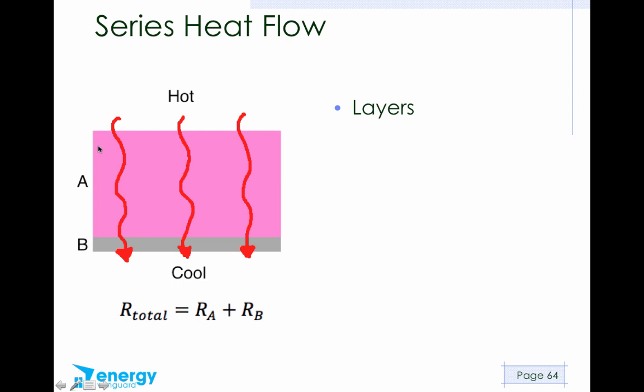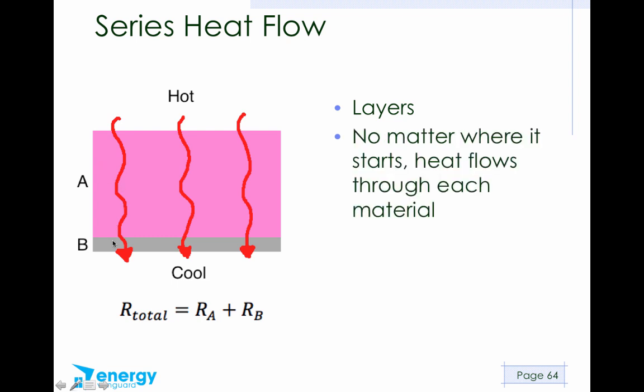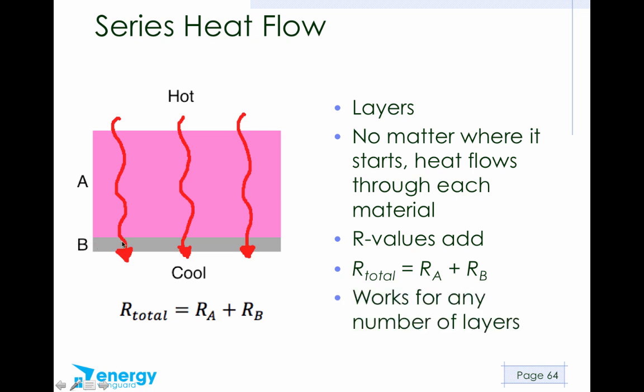That means that the amount of heat flow is going to be the same no matter which path it takes, and the R values will add. So the total R value is the R value of layer A plus the R value of layer B. That's our total R value. It doesn't matter how many layers we have. We could have 100 layers. We would just add up all the R values.